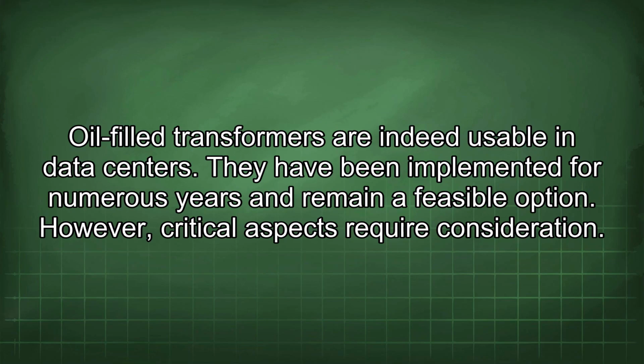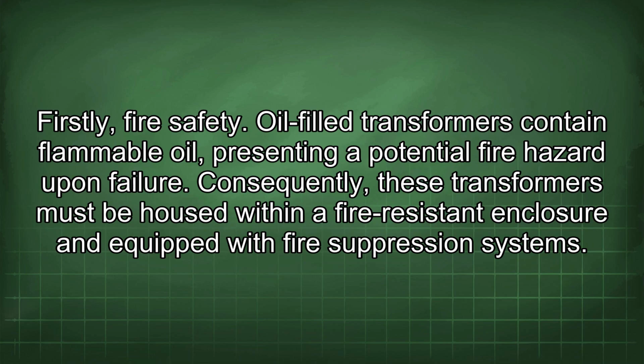Oil-filled transformers are indeed usable in data centers. They have been implemented for numerous years and remain a feasible option. However, critical aspects require consideration. Firstly, fire safety. Oil-filled transformers contain flammable oil, presenting a potential fire hazard upon failure. Consequently, these transformers must be housed within a fire-resistant enclosure and equipped with fire suppression systems.